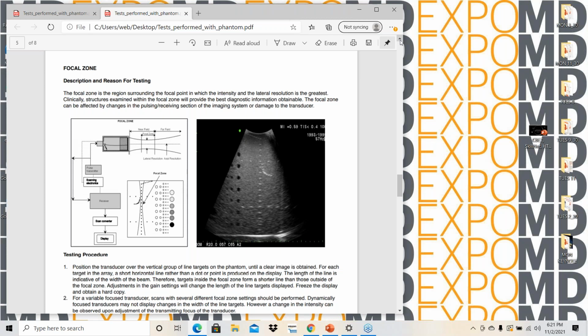This is a Philips, which I would normally associate with a bar, but because it's a portable system, it has an arrow. So you just have to look at it and realize if it's a bar, you can adjust the size of it. And you can pinpoint it to one dot, one focal zone, or you can make it very wide so the whole screen is your focal point, if you will. The problem with making it really large is that it extends the refresh rate. So if you're looking at a moving object, it's going to get very chunky because you've made it such a large zone, the refresh rate goes way down.